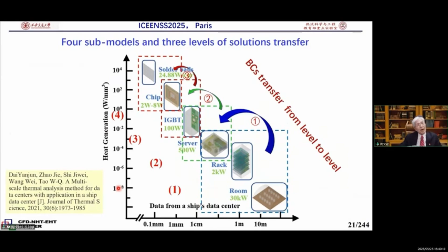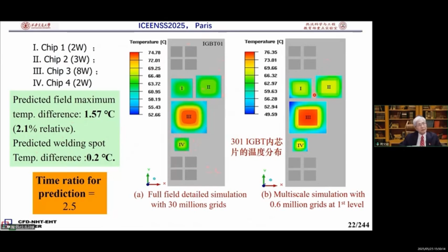Now we make an interesting comparison. For the one-rack situation -- note, one rack, not 15 racks -- we used a very fine grid system with about 30 million grids for the total field, making a very detailed simulation. For another method, on the same one rack, we used the mathematical multi-scale simulation I presented before, with 4 submodels, and compared the results. The predicted maximum temperature difference in the field was only about 2.1%. The predicted welding spot temperature difference was only 0.2 degrees C. But the time spent on the very detailed simulation was about 2.5 times that of the mathematical simulation.